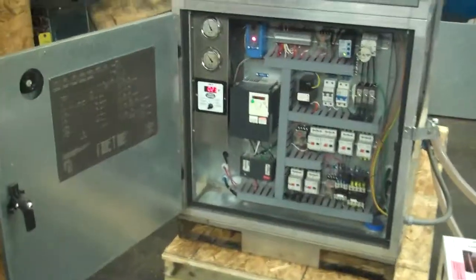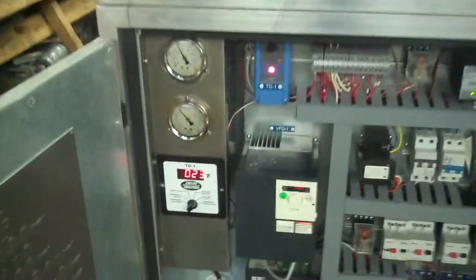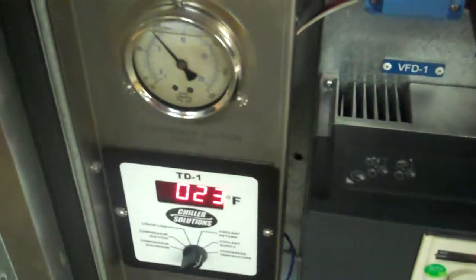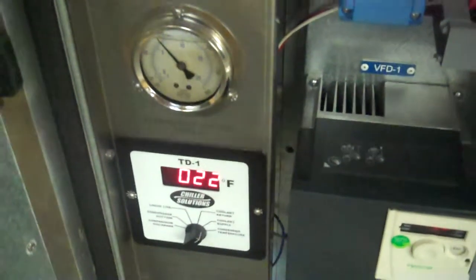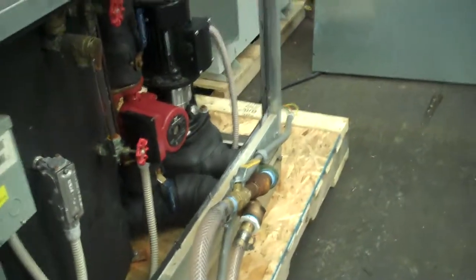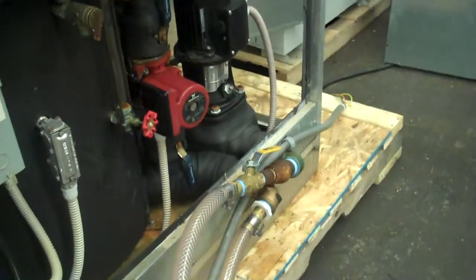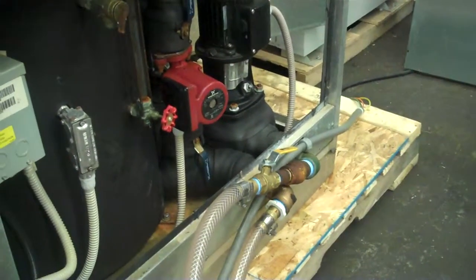This is our video number 2 as we're starting to approach our set point range. We're down to about 23 Fahrenheit. Again, right now in our shop we have a 30% glycol solution. We really recommend, or whoever gets this really probably should be running a 50% solution, especially if this is going outside in a colder climate.